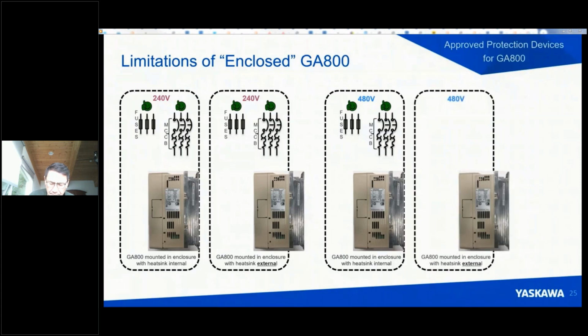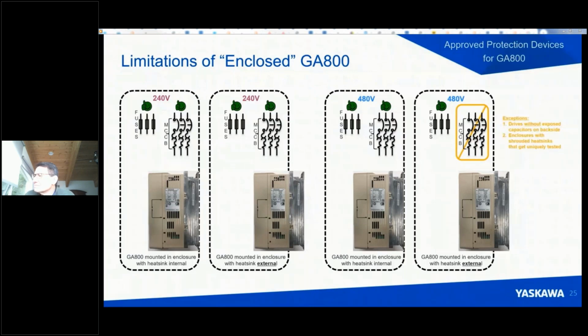But then when we go to a 480 volt drive with the heatsink external, and we apply fuses as the device, that's a thumbs up, that's good. But the circuit breaker, in the eyes of Yaskawa, and the same would apply for the 600 volt drive, is that we don't really like to see this as a protection method with heatsink external.